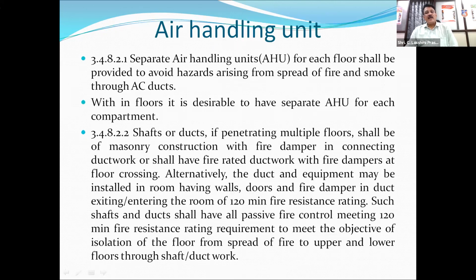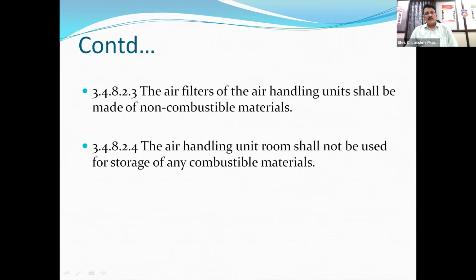Then separate air handling units for each floor. Shafts or ducts, if penetrating multiple floors, shall be of masonry construction with fire dampers in connecting ductwork, or shall have fire rated ductwork. This is very, very important. Then the air filters of the air handling unit shall be made of non-combustible materials. The air handling unit room shall not be used for storage of any combustible materials.